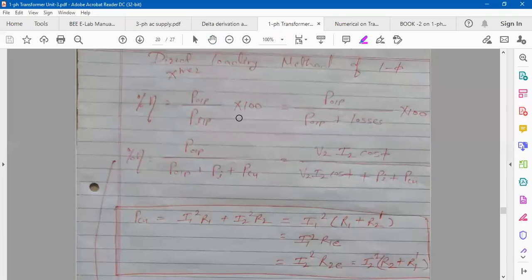Yesterday we saw the direct loading method, which is used to calculate efficiency and voltage regulation. Voltage regulation formula is E2 minus V2 upon E2 into 100. We also saw the graph — for R and L type of load, as you go on increasing the load, voltage across it decreases, E2 is greater than V2, and that's why voltage regulation goes on increasing.